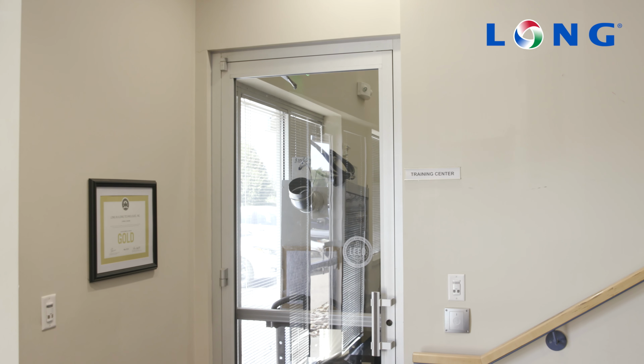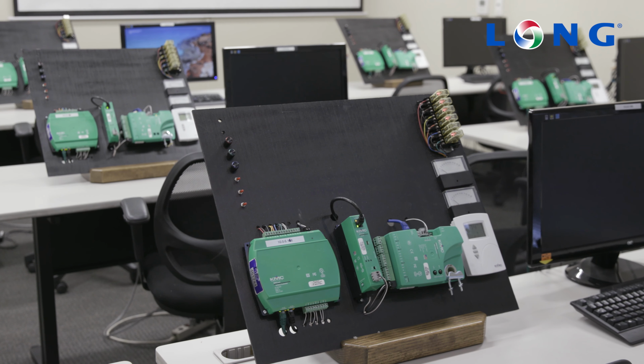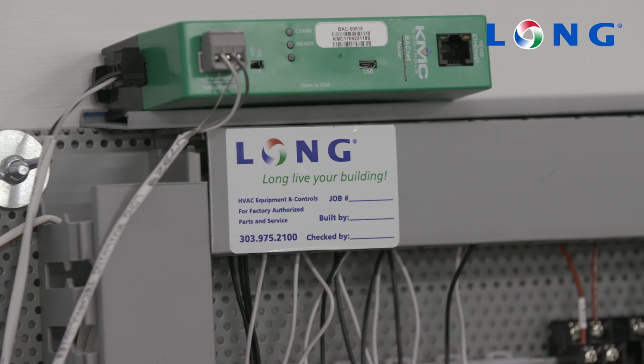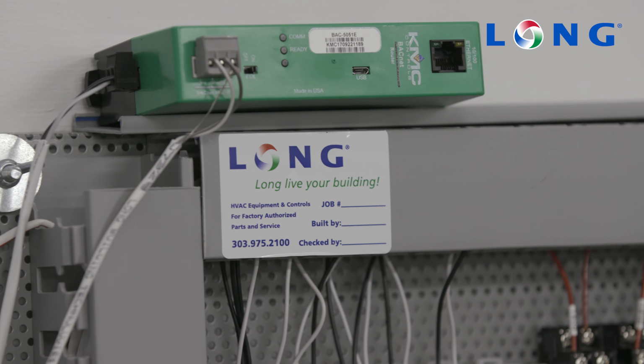The other products that we rep are more difficult to configure, predominantly because they require tunneling through a front end, a supervisor, to connect to a local controller. There's literally a controller where you open up a panel in a chiller plant and you can't plug in directly to it. You have to go back to the front end or have a Wi-Fi connection back to the front end. With KMC, we have the ability to directly connect to a controller with their configuration software directly in a laptop.